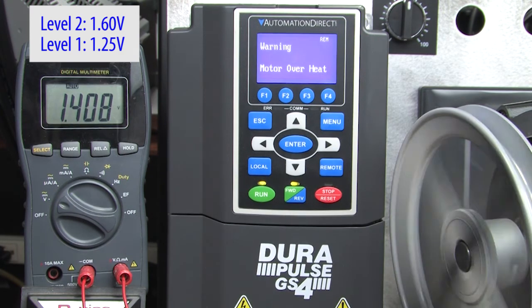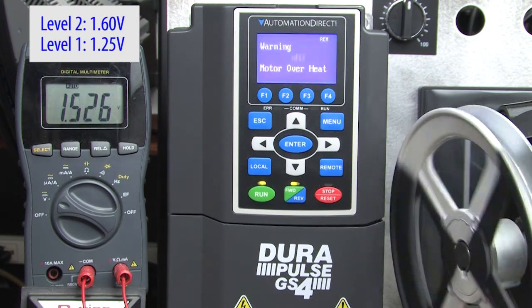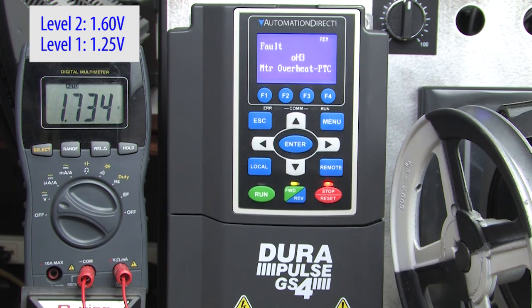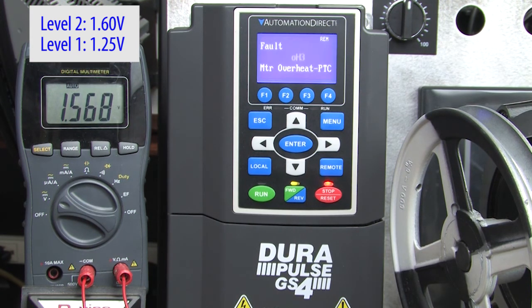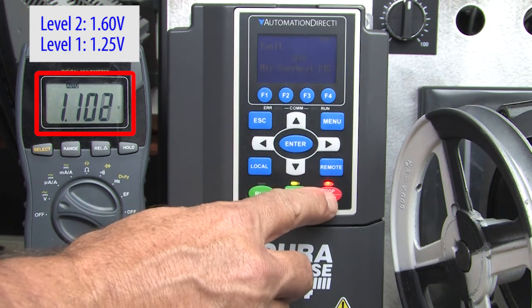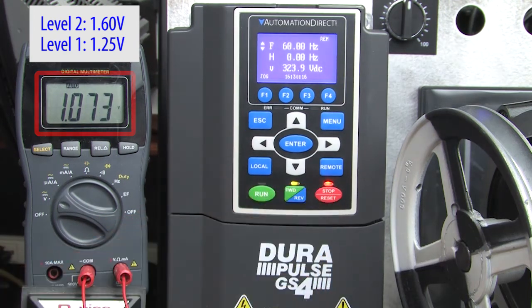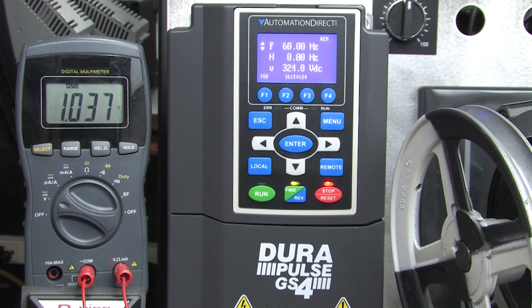Let's keep heating it to level 2. Sure enough, the motor ramps to a stop with no delay. Exactly what we asked for. One thing to be aware of, once the motor hits level 2, it doesn't automatically recover. Even if the temperature drops all the way back to normal. You have to clear the fault. I'll hit the stop on the keypad, but you could also clear it remotely from a PLC for example.